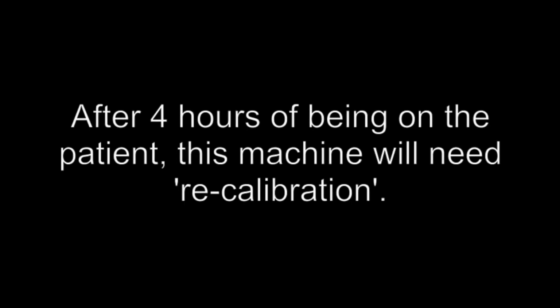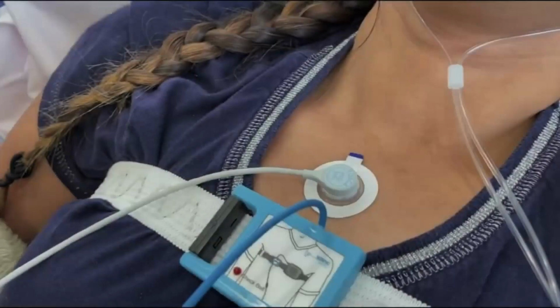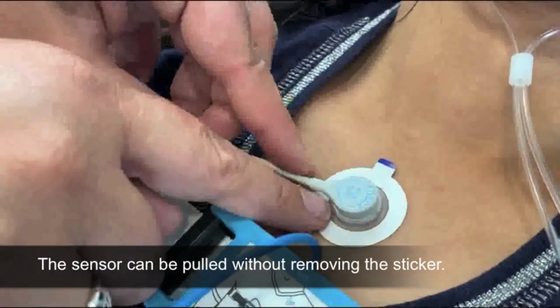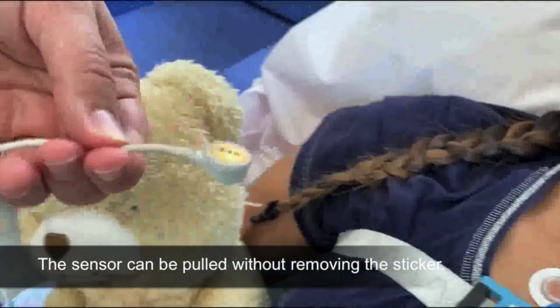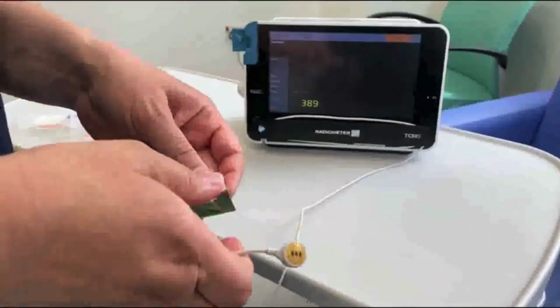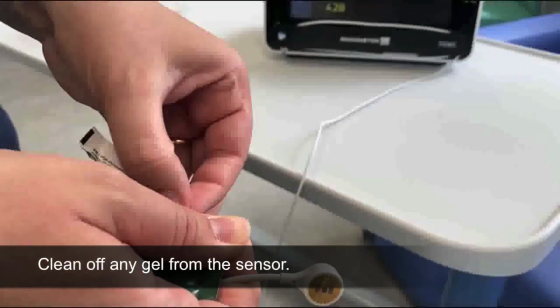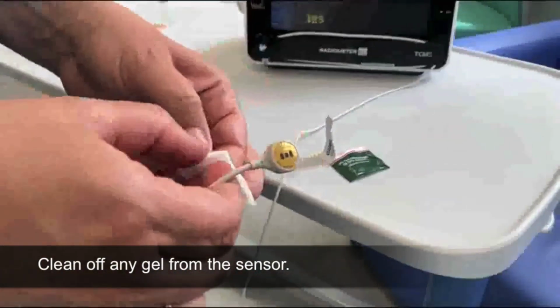After 4 hours of being on your child, this sensor will need recalibration. This will require removing the sensor from your child, performing recalibration, and then placing the sensor back onto your child afterwards. The sensor can be pulled away without removing the sticker. Clean off any gel from the sensor using an alcohol wipe.